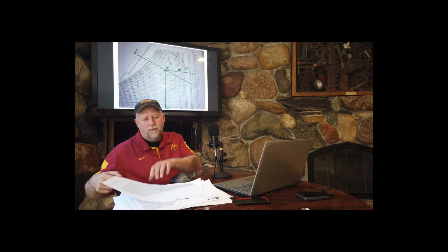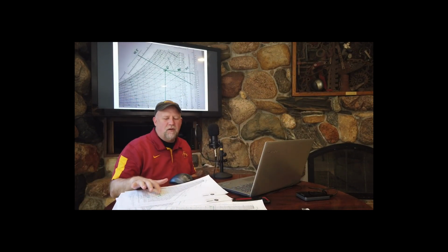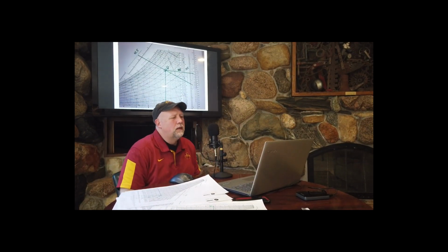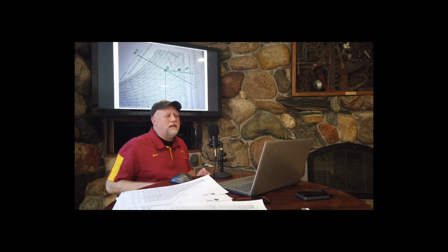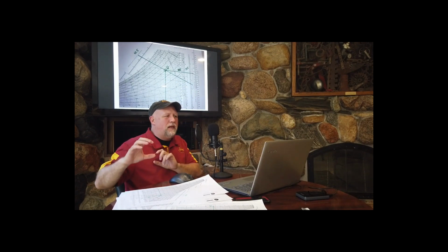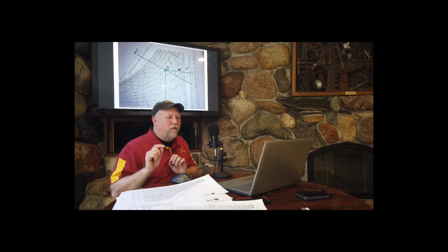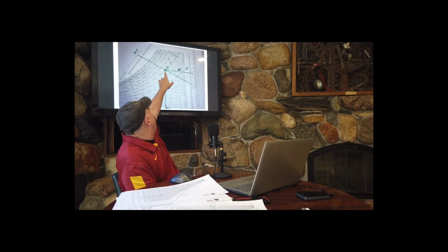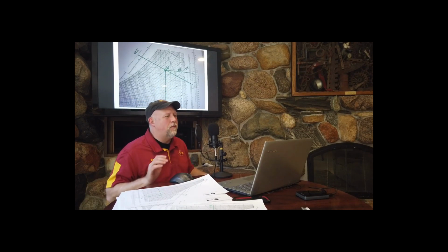Did the same thing here. At 95 degrees Fahrenheit, 50% relative humidity. Just plot that. Now, I use 50% relative humidity because I wanted to illustrate the differences with the same relative humidity at different dry bulb temperatures. That was the whole purpose of this. For this class, our design outdoor air temperature is 95 and 78 wet bulb, so it'd be just a little bit lower. But I just wanted to show you what it looked like at 50% relative humidity.